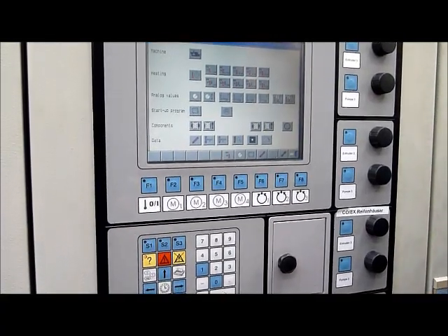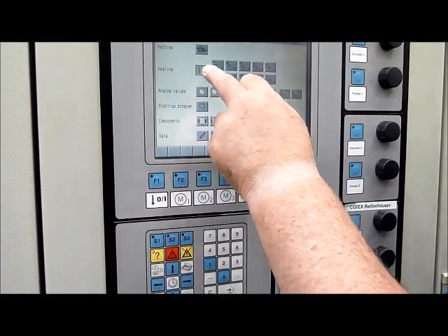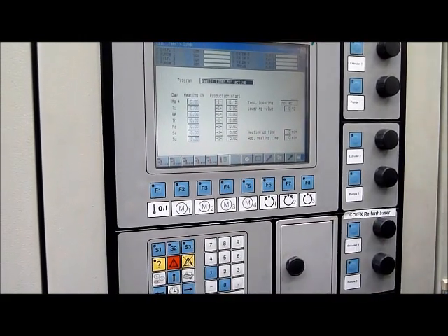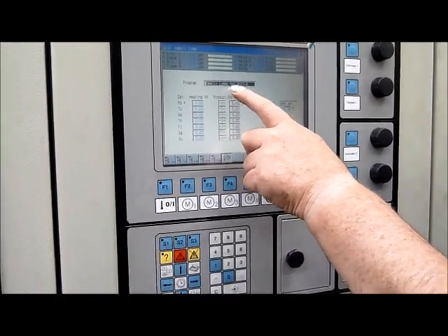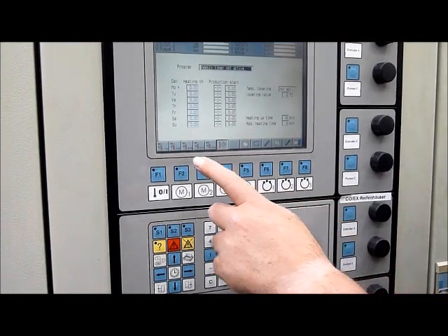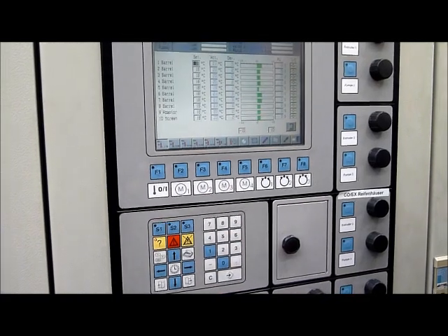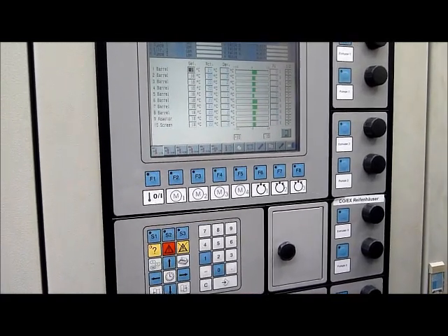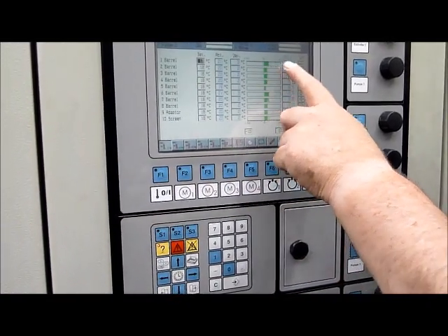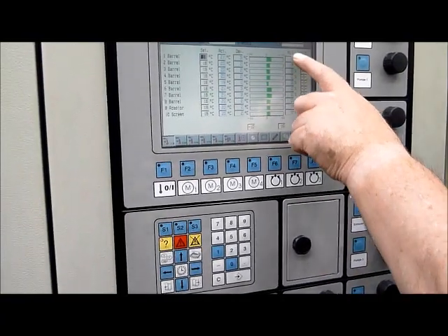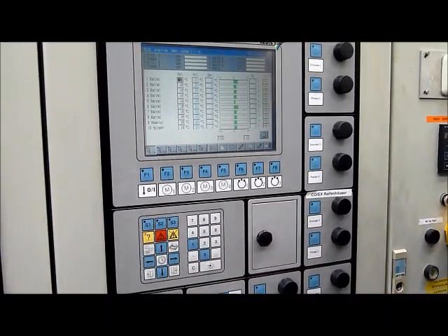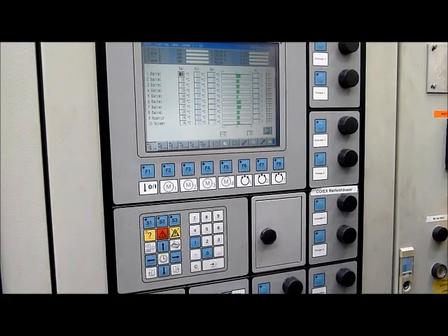So for instance, temperatures or heating, that'll give you your Monday to Friday schedules with temperatures on if you want them, or weekly timer not active, which means they'll be on all the time. So you can go then to group 1, and those are all the temperatures as they stand at the moment. Set point, actual, the deviation, that's plus or minus 10 round set point, percentage output of the heating, or cooling if there's cooling involved. So it'll go 100% to minus 100% if cooling's involved.